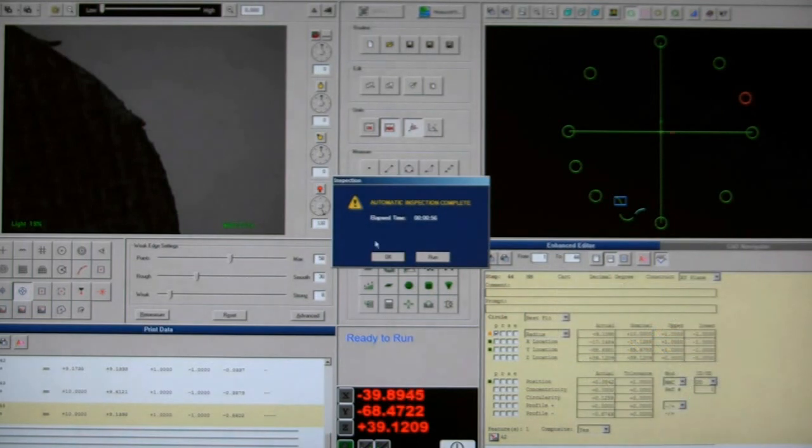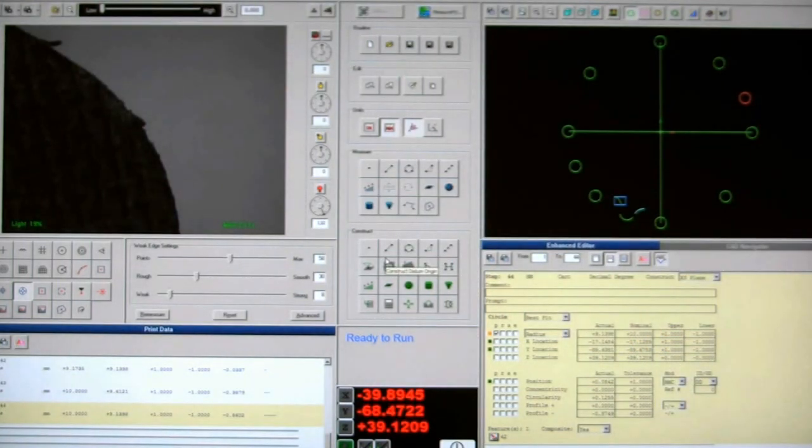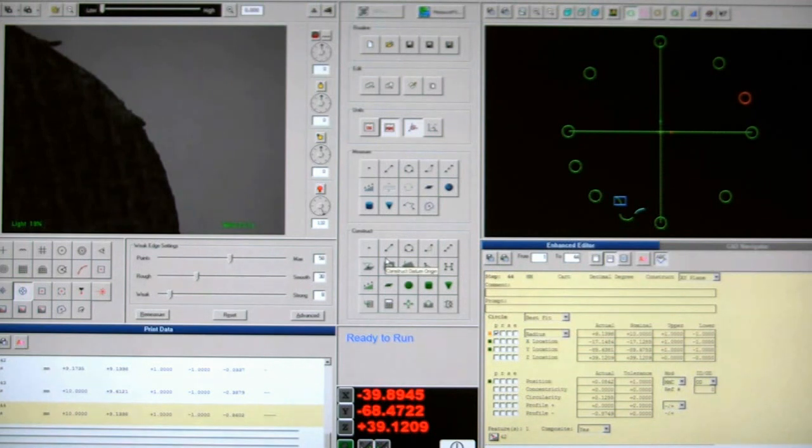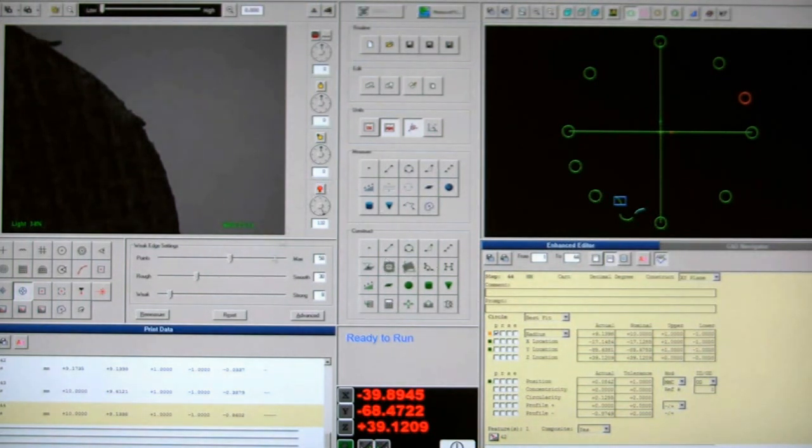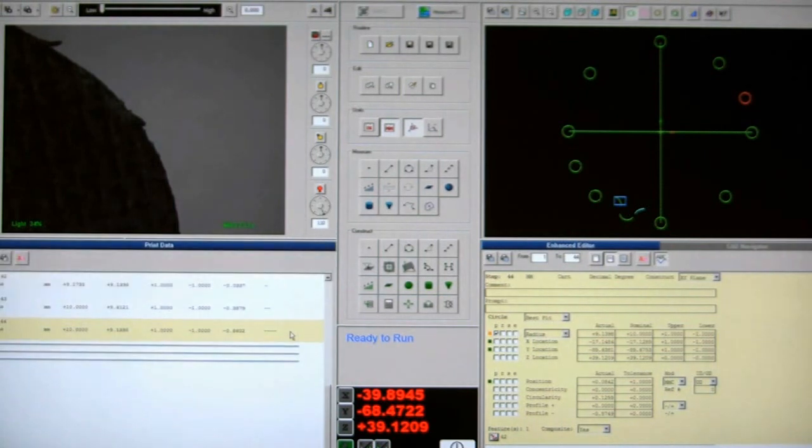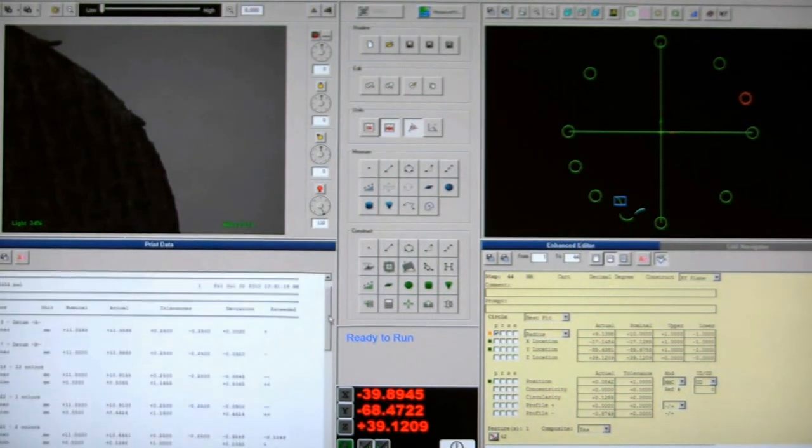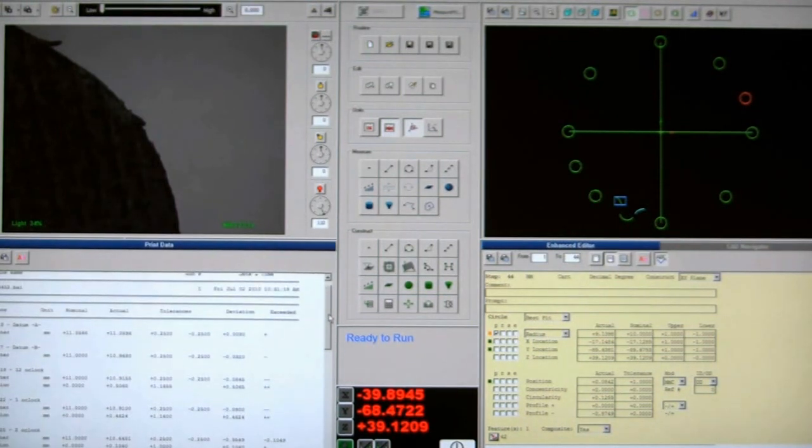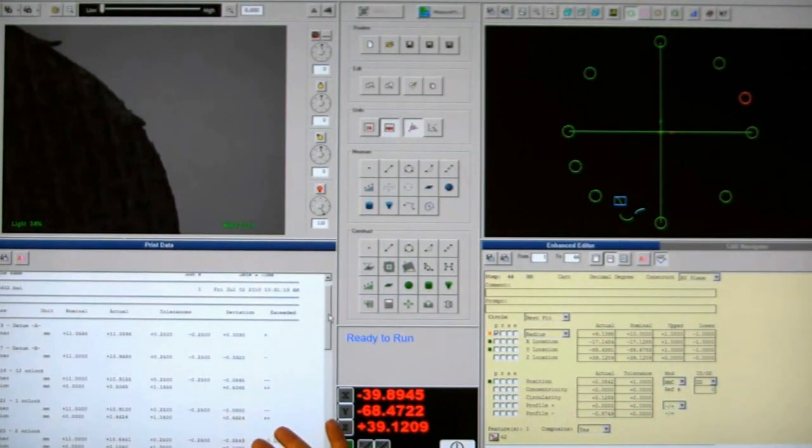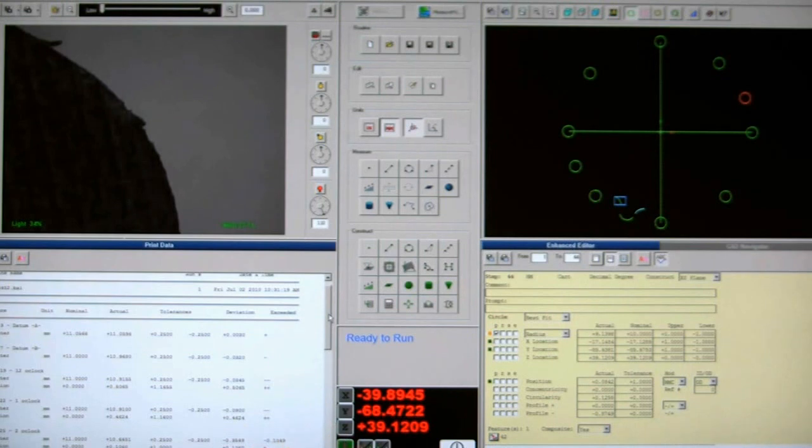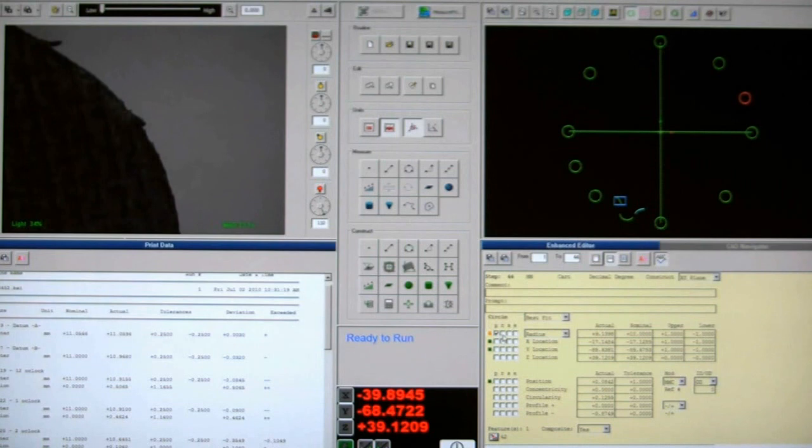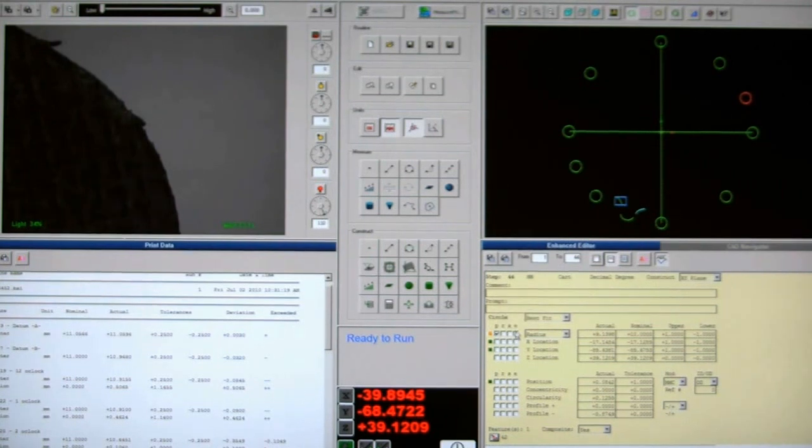That's the part inspection for all four parts. We're doing this in our single monitor user interface which is showing us everything that we have on the screen. I'm going to click on the title bar. This is the results on the left-hand side for the measurement. Your program steps are on the right side. And here we can set the nominals and tolerances and also send it to a printer, a report, statistics, or export it to any logical database.